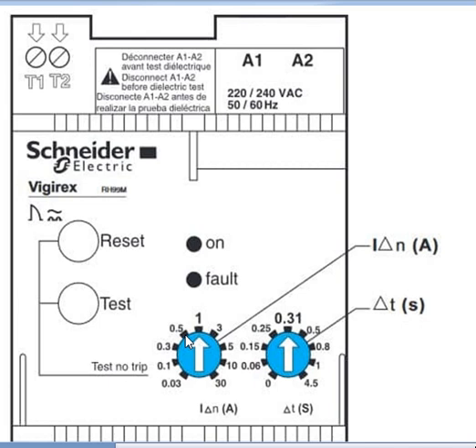You will see these two dials on every relay. If it is Schneider or any brand of relay, you will see two types of dials. One is written I delta N and one is written delta T. The first you can use to set any change in the current, and the next is used for time. Friends, if there is any earth leakage in the circuit, the relay is going to stop supply to the load and it will trip the breaker.